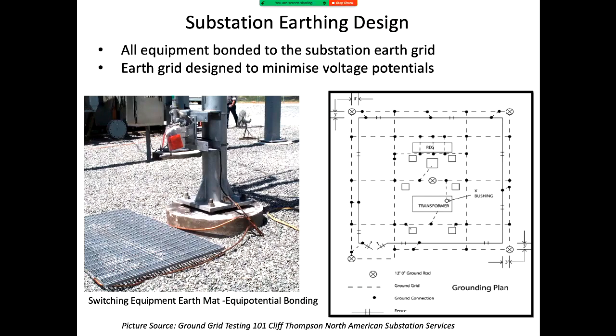So here is an earth mat. What it's done is it's connected up to the earth system, and then this earth goes up to the actual switch or whatever it is. So it means that if you're holding the switch, as close as possible, your hands are at the same potential as your feet.